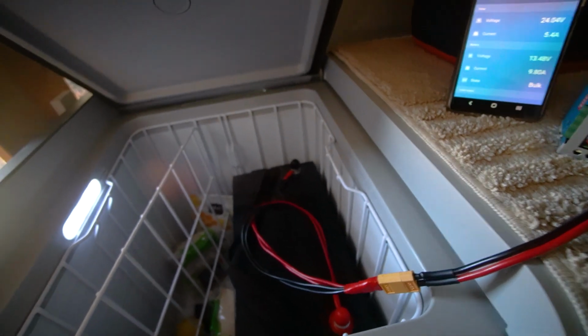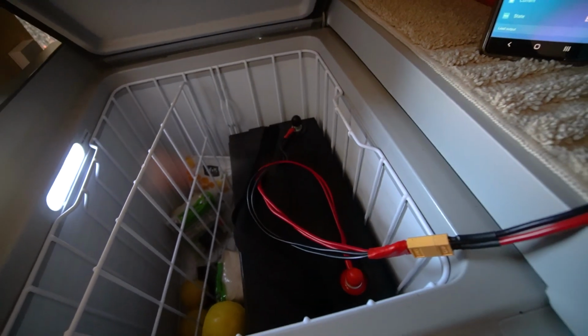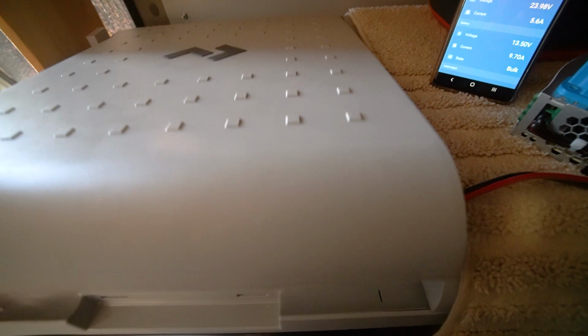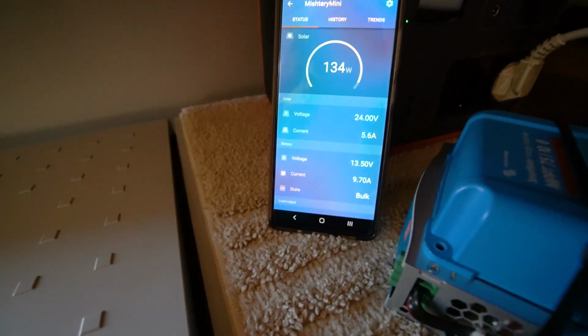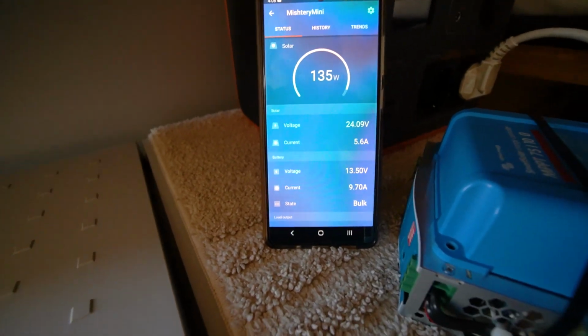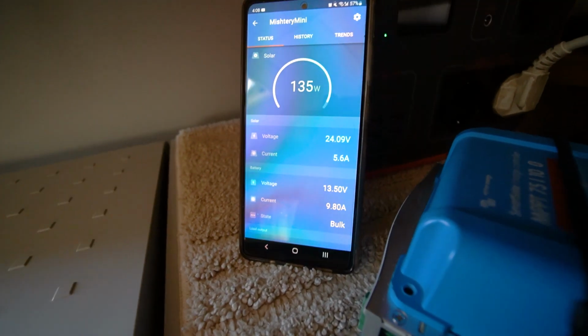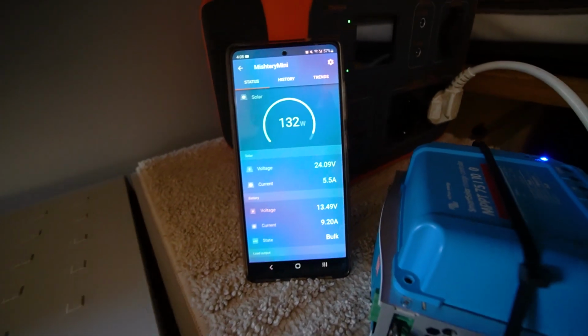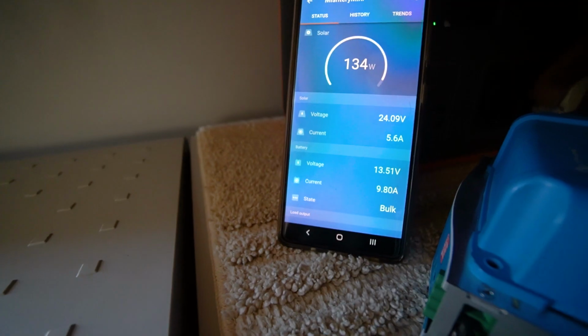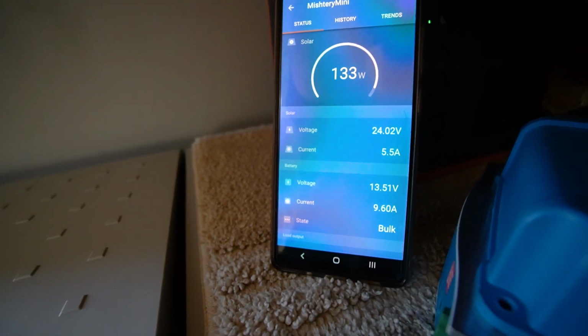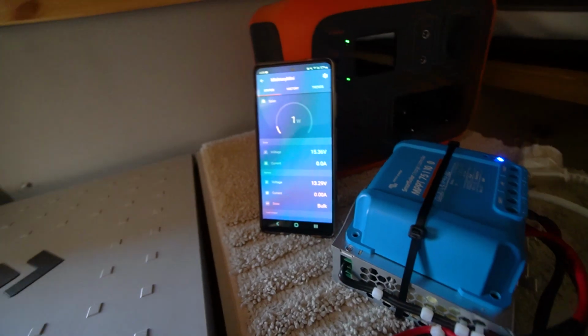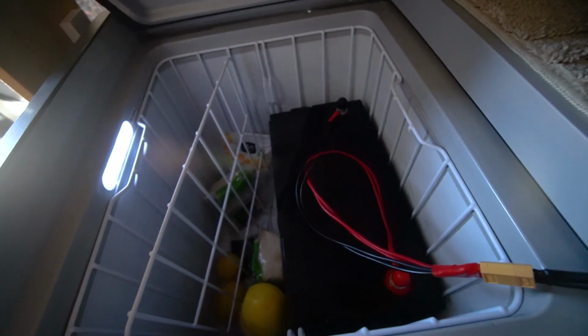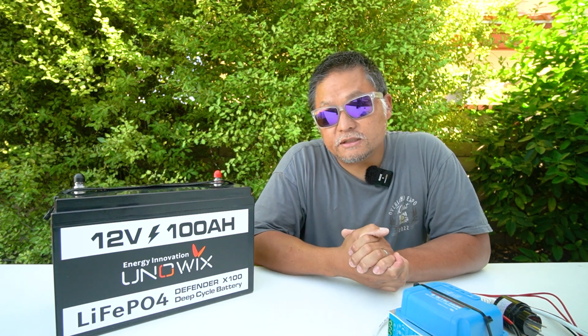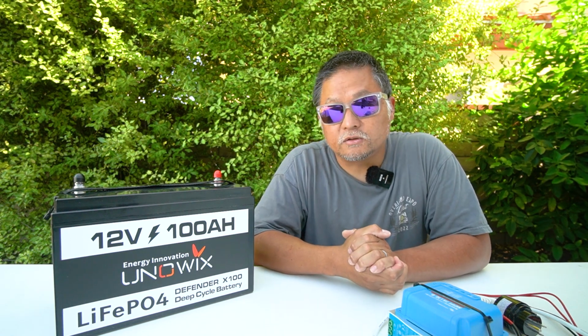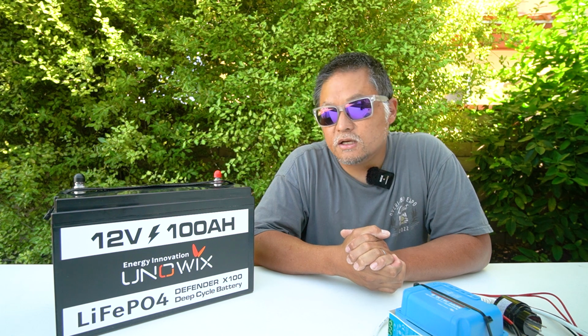Well, that's unfortunate, but I will ask the company about it to see if there's something I'm not doing correctly, or if there's a different setting. The low temp charging protection really should have tripped. So I'm not going to risk damaging this battery by continuing to charge it. Unfortunately, I could not get the cold temperature disconnect to work.